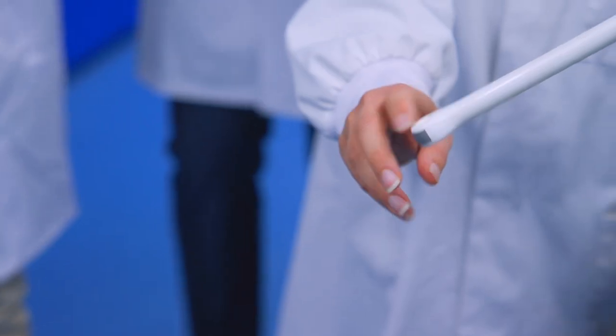So we test the probes like when, as you said, the user is not having a good day, so they push it hard. All these might affect the life of the probe. So you're using real probes from real probe manufacturers, real Trophon machines, and essentially roughing them up a little bit along the way just to account for that real world handling. Exactly.